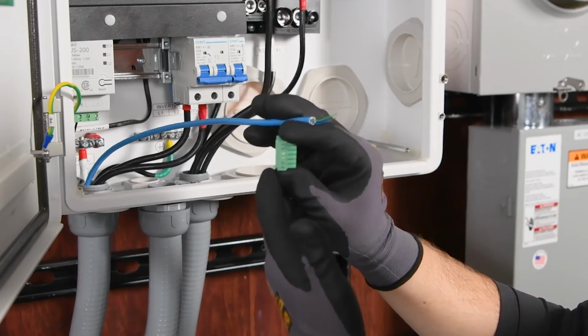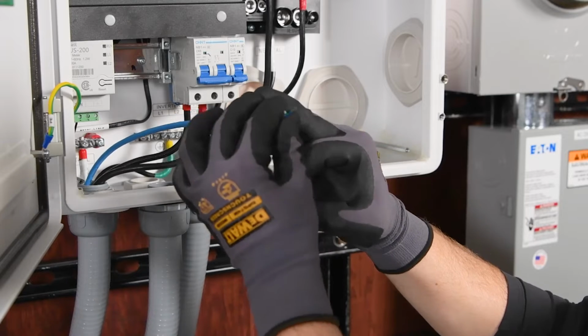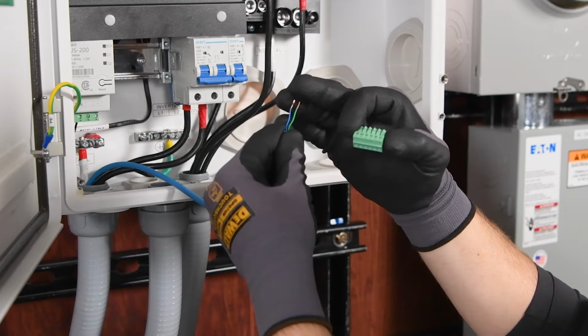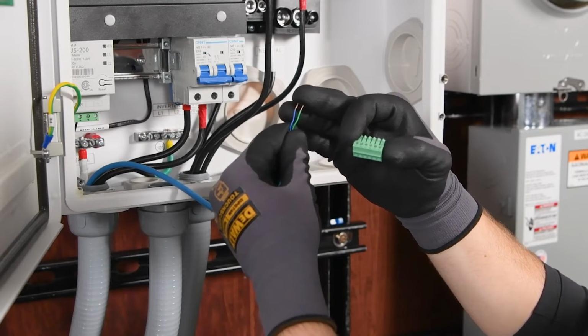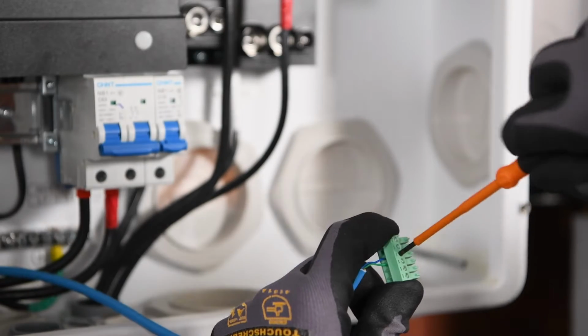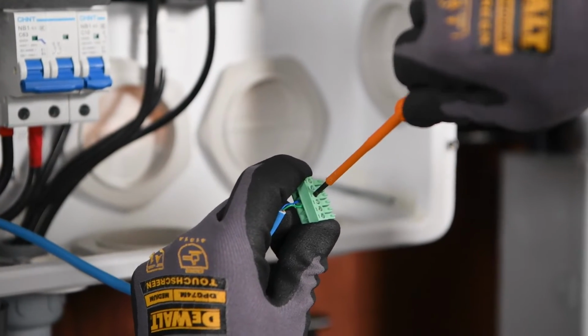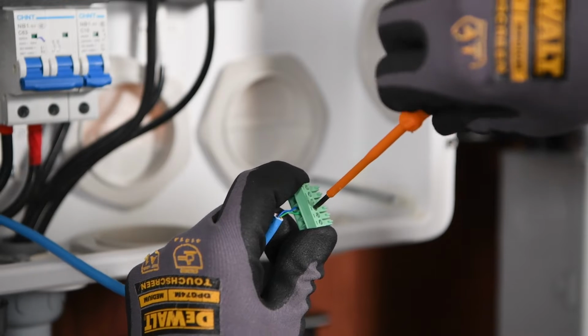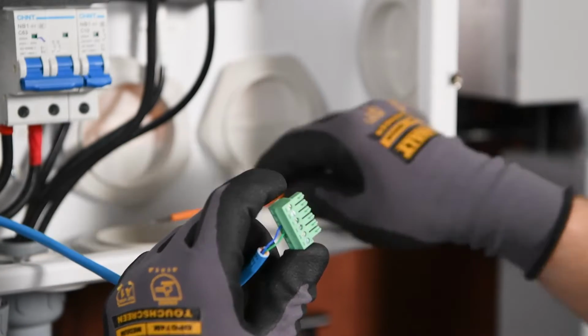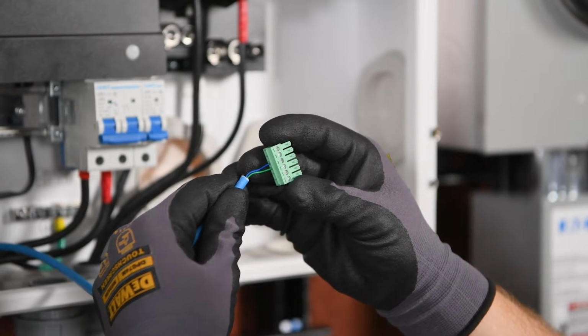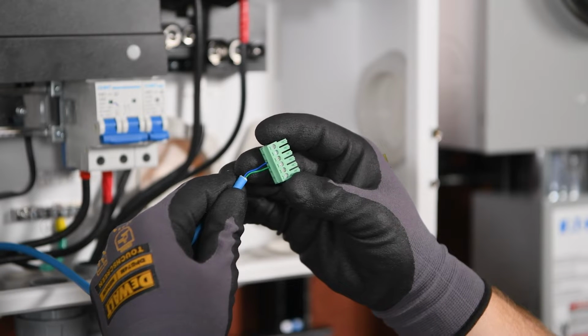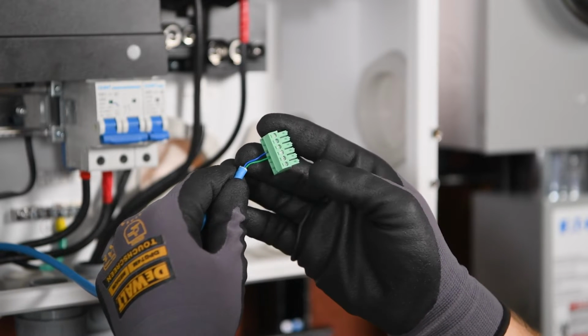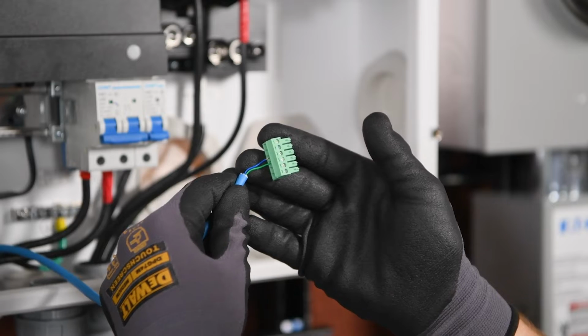We have a 6-pin terminal block here. Again, we have a blue and a green wire. These actually connect to the Growatt 11.4. The blue and the green will go into the 2 in the middle, where blue is on top and green is on bottom. So something as shown here, where we're using the 2 in the middle of our 6-pin connector, and the blue is on top and the green is on bottom.